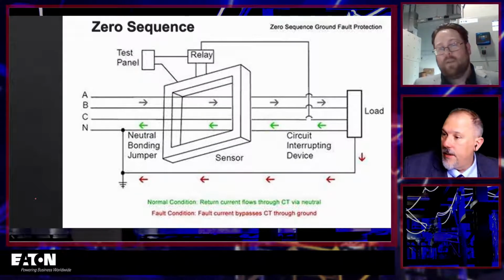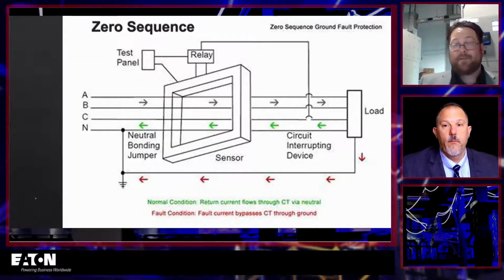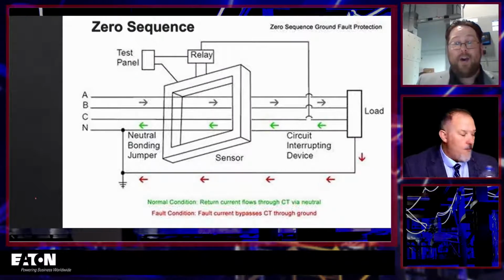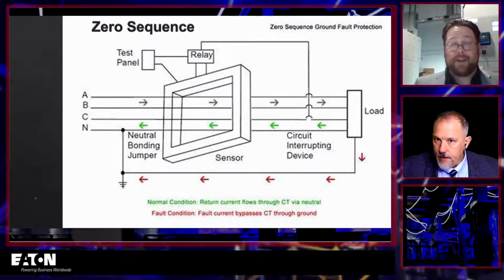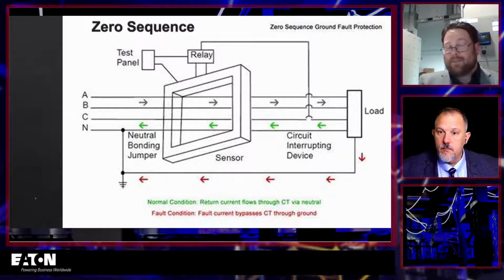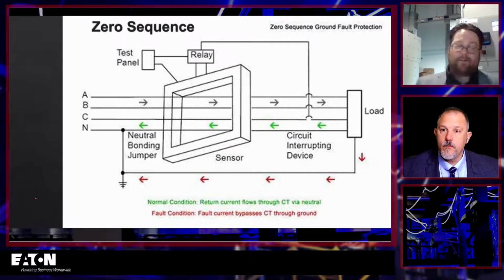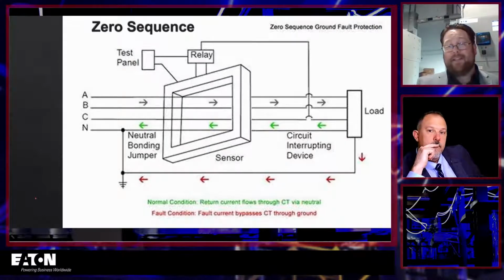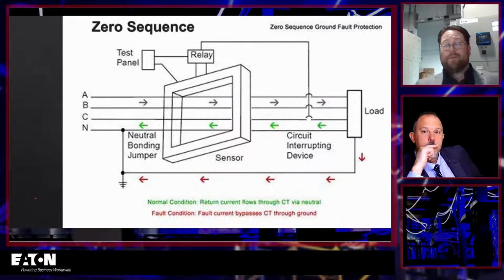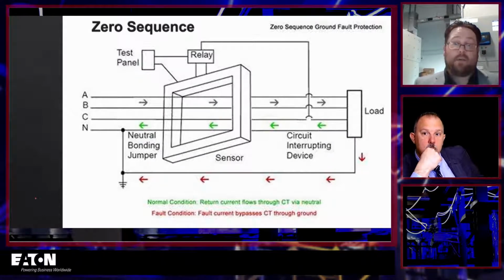Gotcha. Okay. Now once you've done this first install, the code doesn't have a requirement for the primary injection testing later on, right? That's right, only for this first install of the whole system. So typically, what we see is after you do this test for first install, every test after that, you could do primary injection. And at that point, it would be a lot easier to just pull the breaker out and just test the brains, the trip unit of that breaker, or your relays, etc. Or you could ultimately go to secondary injection testing or functional testing. Those are all acceptable per code right now.